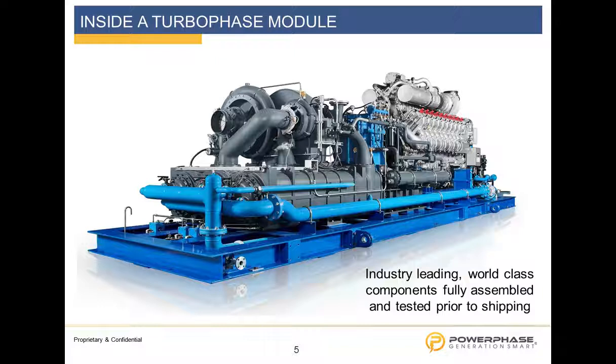Caterpillar engine, and you see a SIAD compressor, which is made in Korea. We've also used a Hyundai and a Samsung compressor. These are all purchased, world-class components. Thousands of them are in existence with millions of fired hours on them, and we're just using them for a unique process. Typically, you see these engines in marine applications as well as genset applications. The compressors are used in everything from instrument air compressors to medical grade dry air, because they are an intercooled compression cycle, which removes all the humidity from the air. A little side note: we make about 3 liters a minute of clean, fresh water when we compress the air.